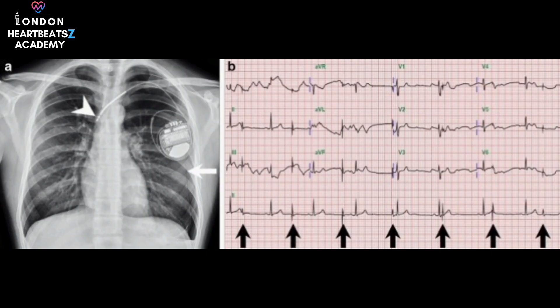Additionally, pacemaker interrogation, checking the device's internal data using a programmer, can identify dysfunction, like high pacing thresholds or sensing problems. It's important to distinguish Twiddler syndrome from something called Reel syndrome. Reel syndrome is a similar issue but results from inappropriate anchoring of the leads during the implantation surgery itself, where the generator basically spins around its long axis, winding the leads around it. Different mechanism, similar result. How do you fix this once it's identified?